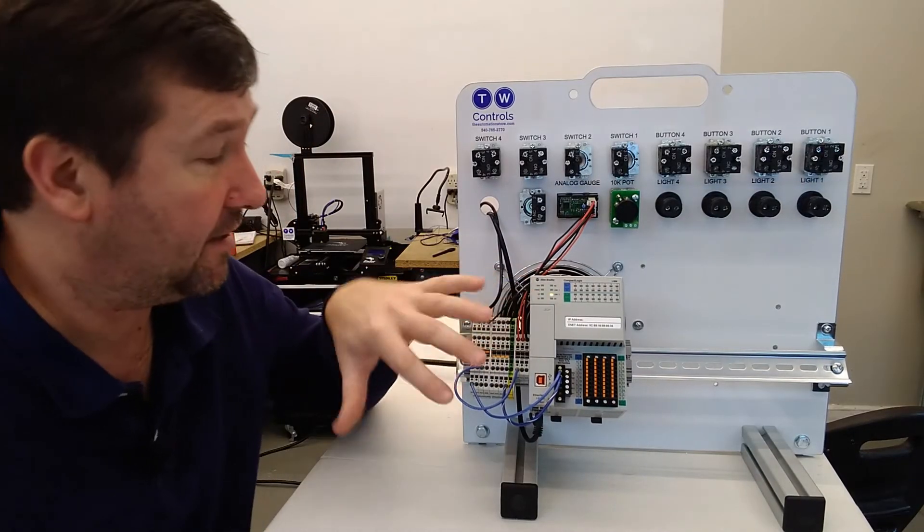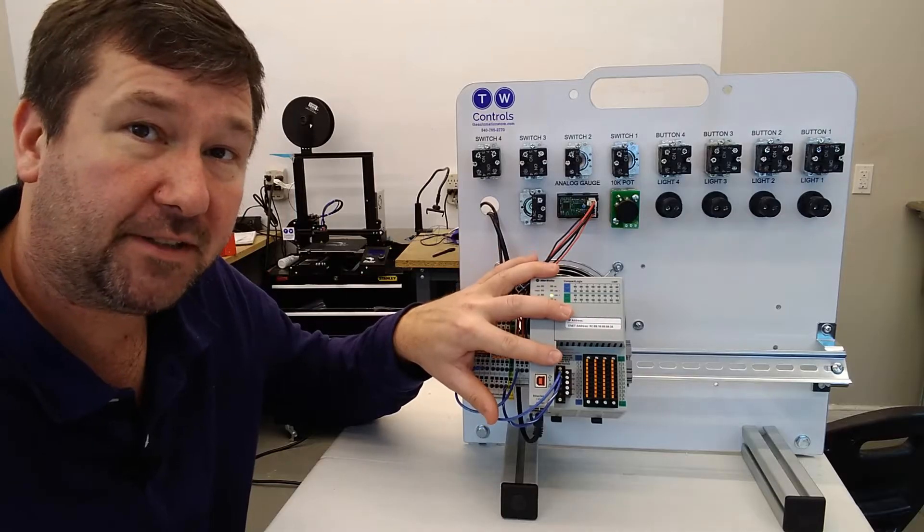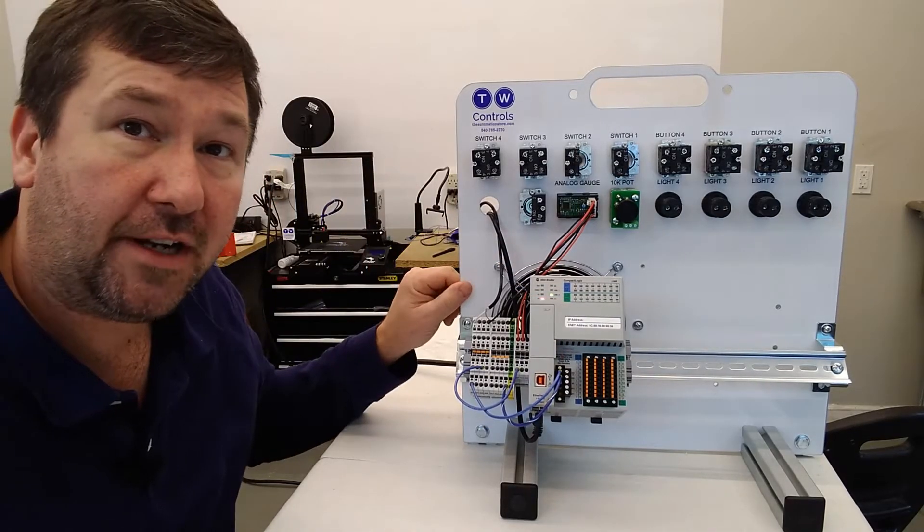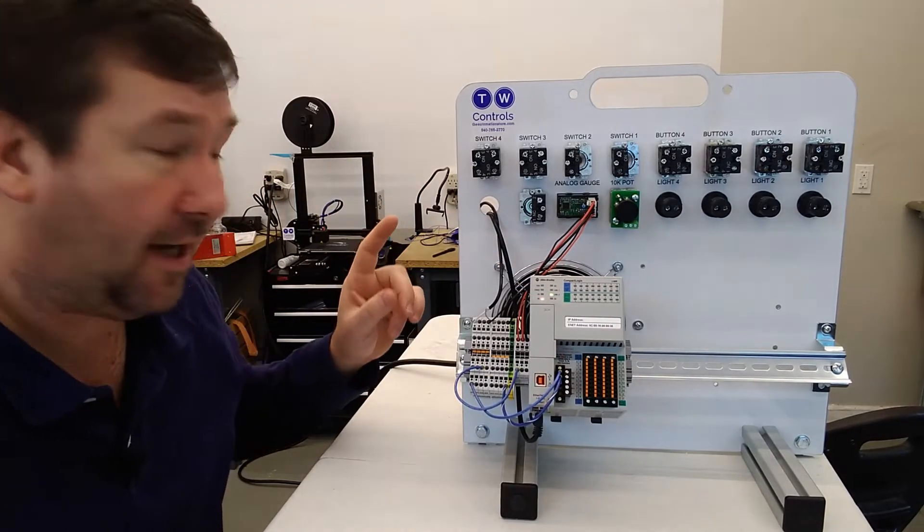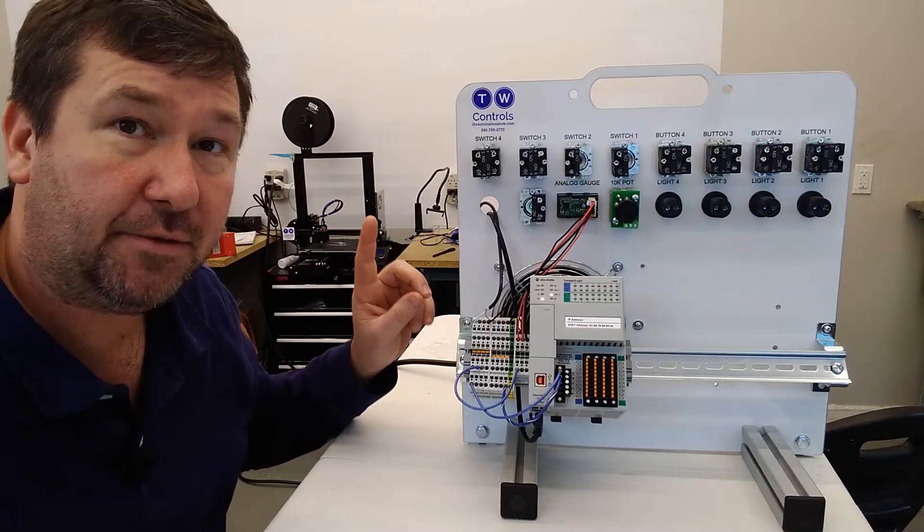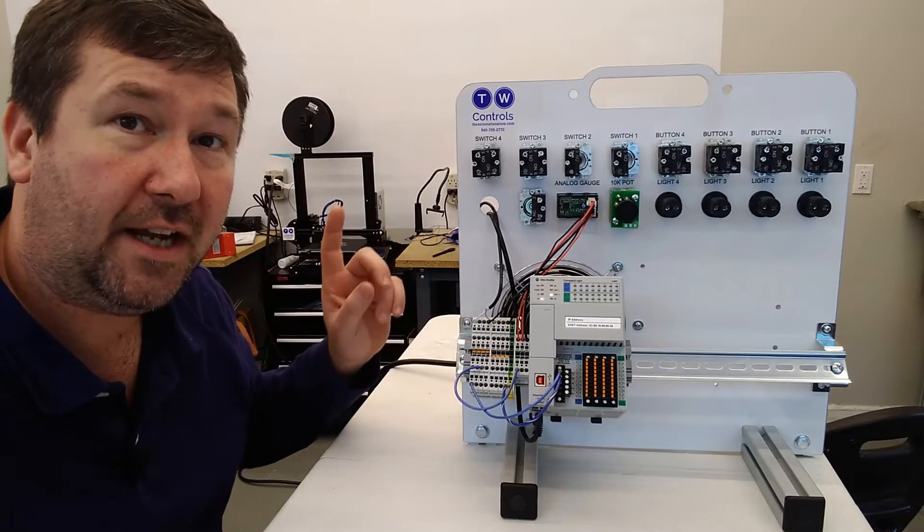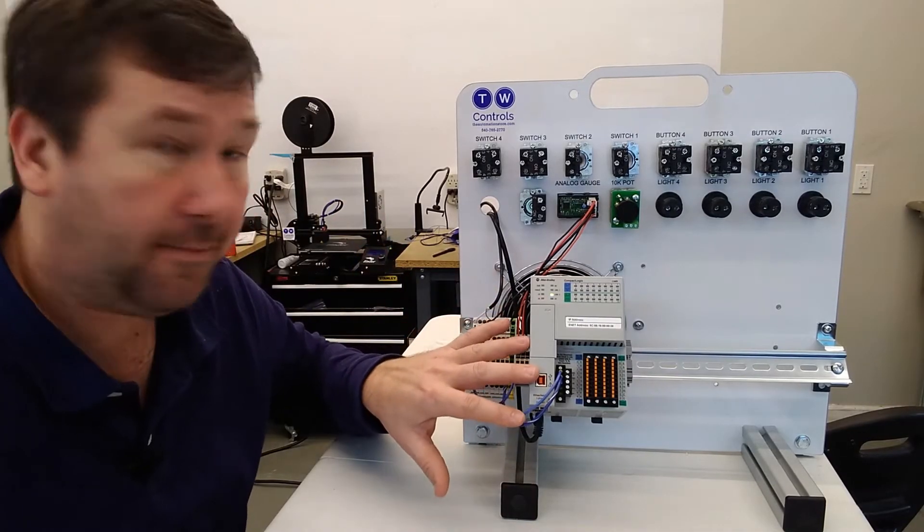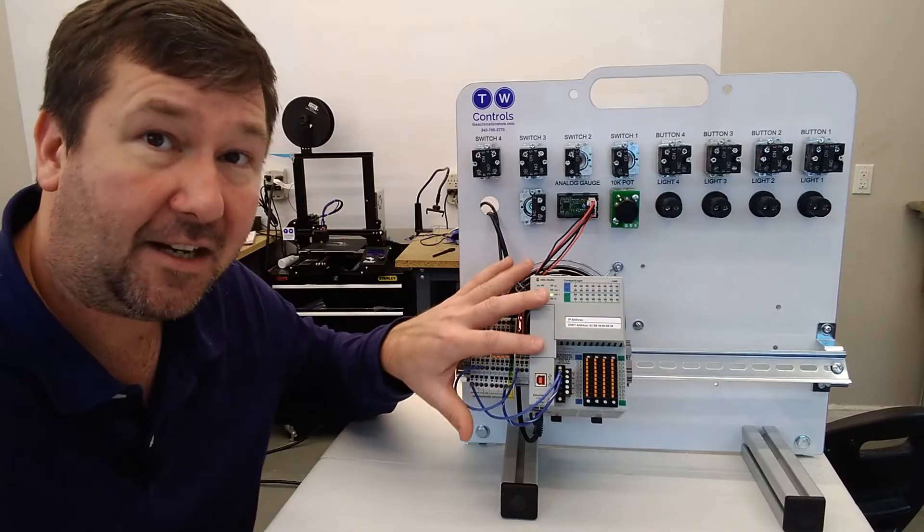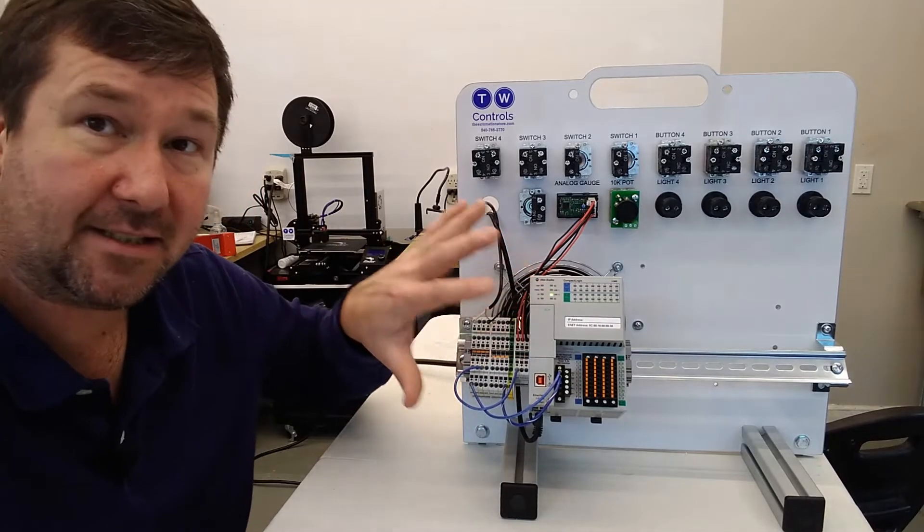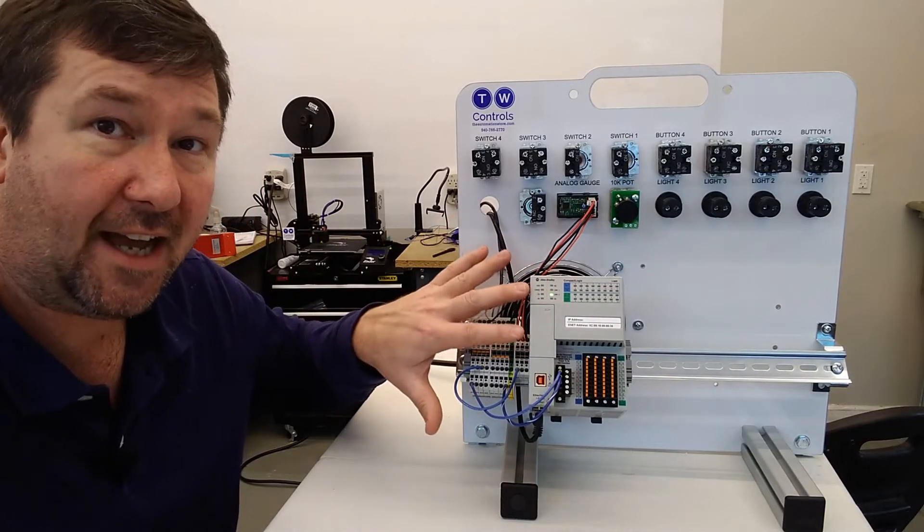The big thing you're going to need is to know the IP address of your PLC. Now if you're using one of our trainers, the default IP address is going to be 192.168.1.10. If you have a new one straight out of the box, it's not going to have an IP address assigned. It's going to be looking for something to assign it.